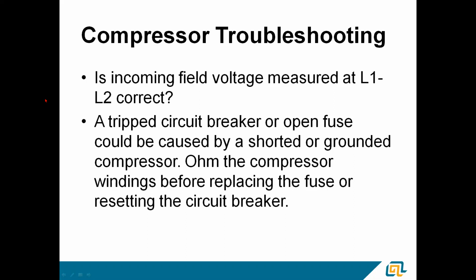First thing you got to know is, is your incoming field voltage correct? Is L1 and L2 good? I got my 240 volts there. We're okay. We can continue. If I don't have 240 volts and I find a tripped breaker or an open fuse, at this point we got to take a step back, take a deep breath, and start ohming stuff out. An open fuse or tripped circuit breaker could easily be caused by a shorted or grounded compressor. So you want to ohm those compressor windings before replacing the fuse or resetting the circuit breaker.